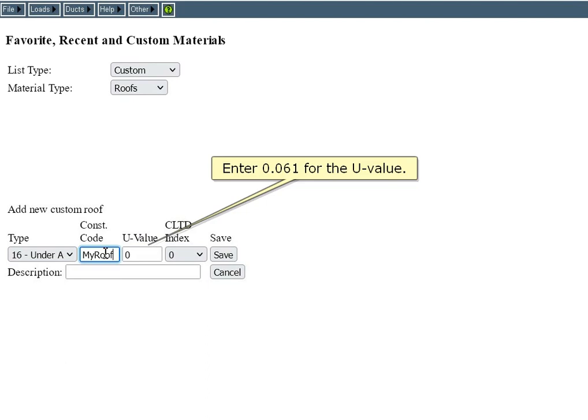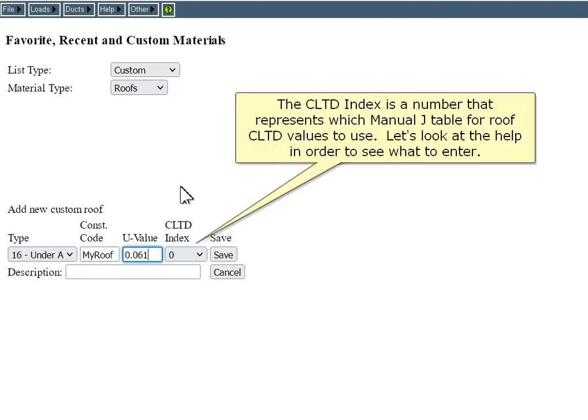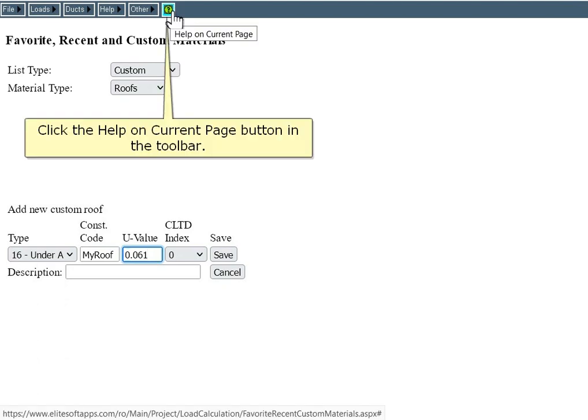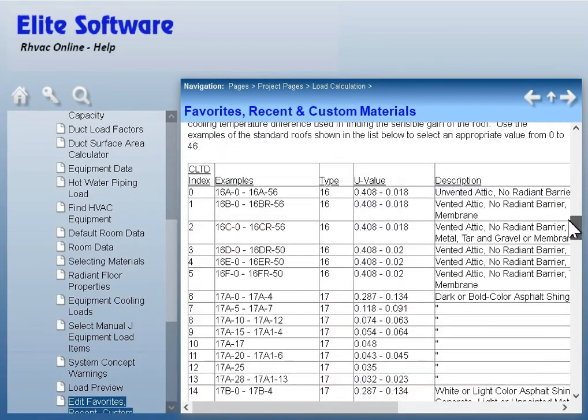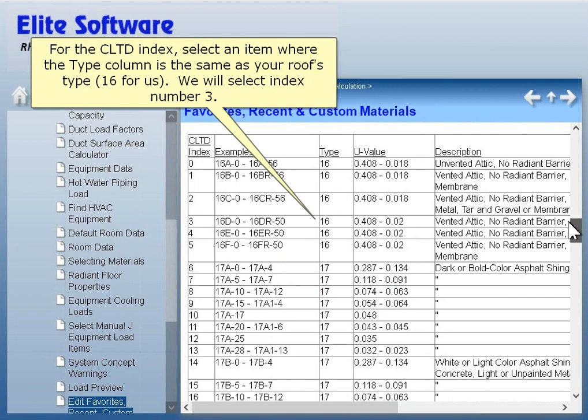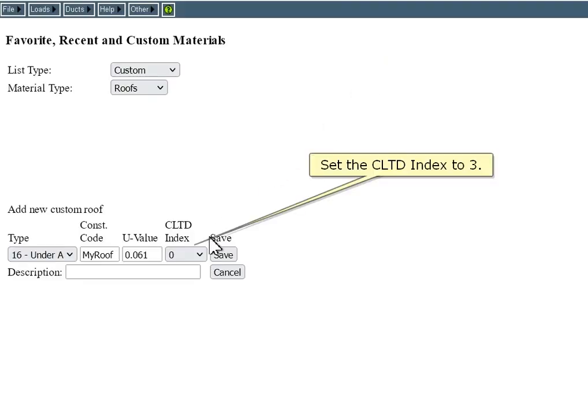Enter 0.061 for the U-value. The CLTD index is a number that represents which Manual J table for roof CLTD values to use. Click the Help on Current Page button in the toolbar to see what to enter. For the CLTD index, select an item where the type column matches your roof's type — 16 for us. We will select index number 3, so set the CLTD index to 3.